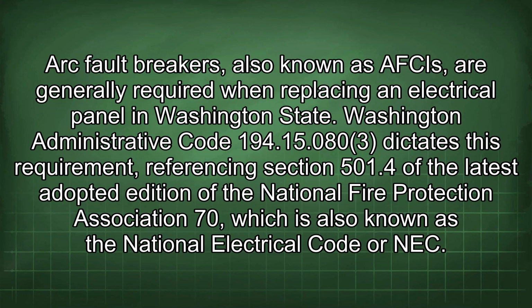Arc fault breakers, also known as AFCIs, are generally required when replacing an electrical panel in Washington state. Washington Administrative Code 194.15.080(3) dictates this requirement, referencing Section 501.4 of the latest adopted edition of the National Fire Protection Association 70, which is also known as the National Electrical Code or NEC.